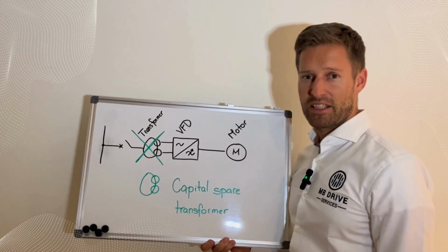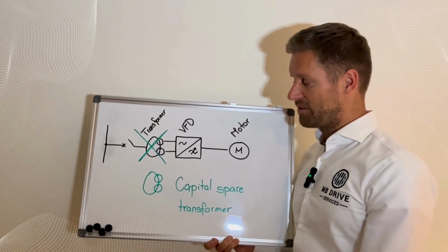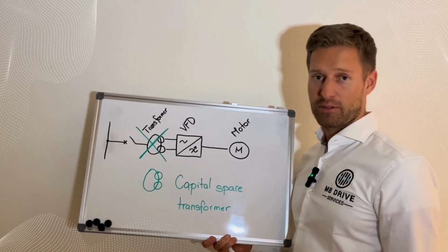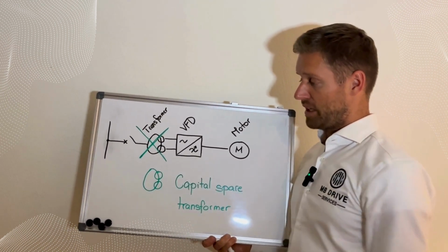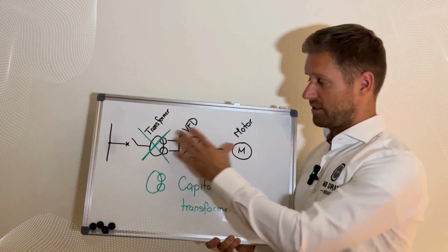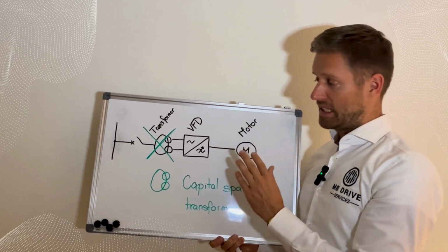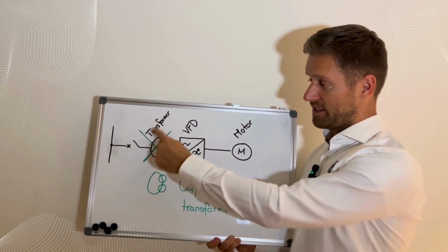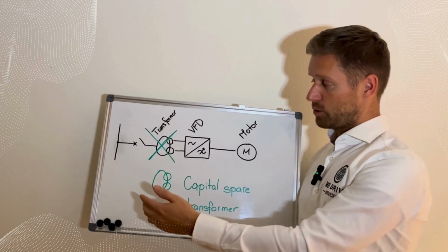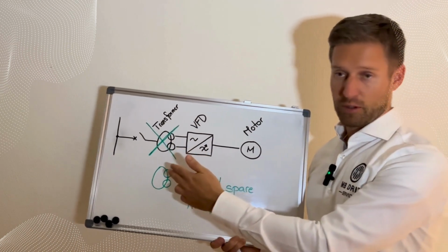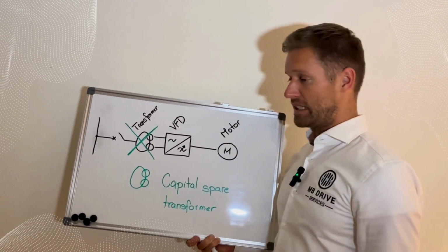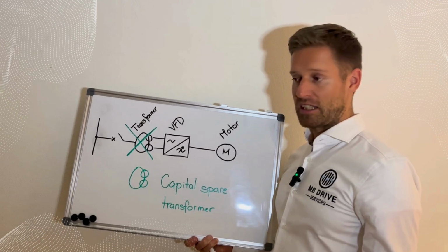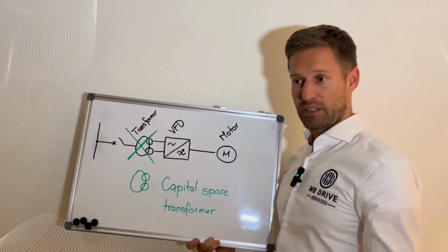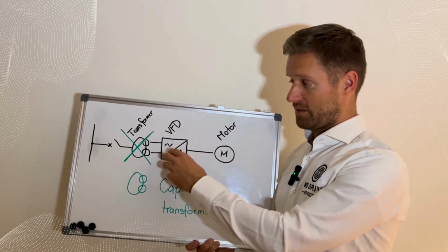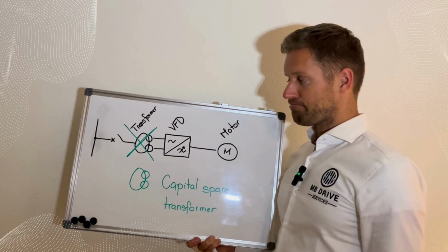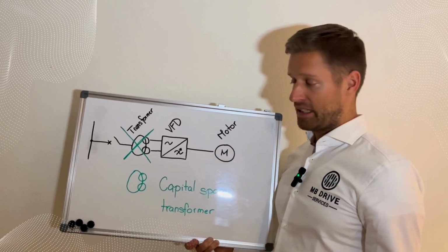During my professional career, I have experienced how difficult it is and dramatic it is for the customer if the main transformer fails. Then basically the whole drive system is down, especially since this is a converter transformer specifically designed for the VFD. It's typically this multi-winding design. It's not a transformer that you can easily rent somewhere. It's a very specific design linked to the specific type of the VFD. So you don't easily find a spare.